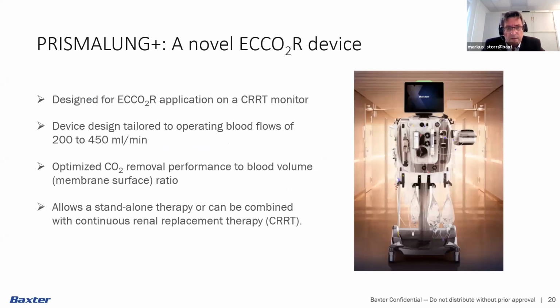So to summarize, the PRISMALUNG Plus device has a design tailored to specifically remove CO2. The device design, including the fluid path and the dimensional parameters, the selected membrane surface area, and the blood flow volume, allows for optimized CO2 removal at the intended operating blood flows of 200 to 450 mL per minute. We could show that, of course, depending on the operating blood flow and the PCO2, carbon dioxide removal rates of more than 130 mL per minute can be achieved with this device.